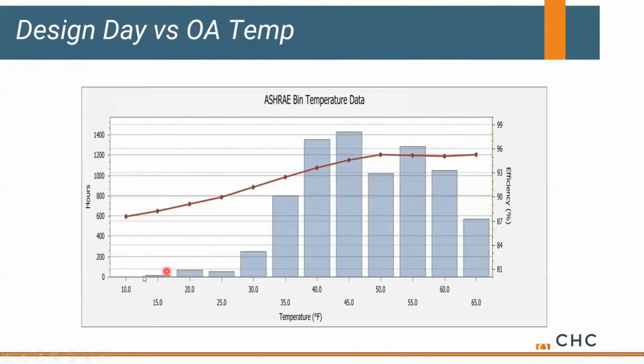But we might spend 4 hours a year at 10 degrees, and the majority of our time is really anywhere from 40 to 55 degrees. Again, I'm referencing Portland. So as weather warms up, we don't need full output from our boiler. We can actually deal with less heat in our building and still heat our classrooms or our offices. So this is typically what's happening. We spend a lot of time with warmer weather. As a result, we don't need our worst case scenario.